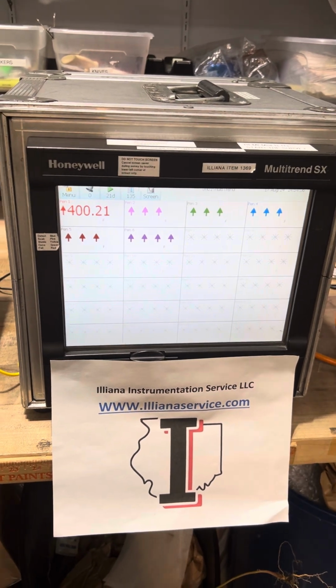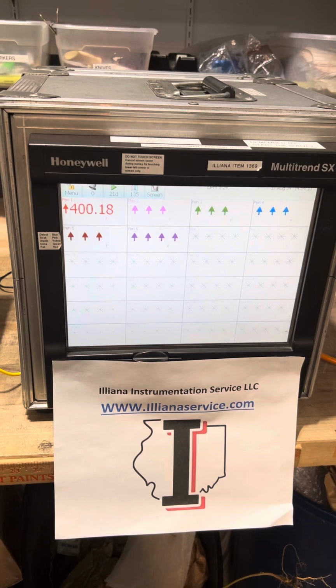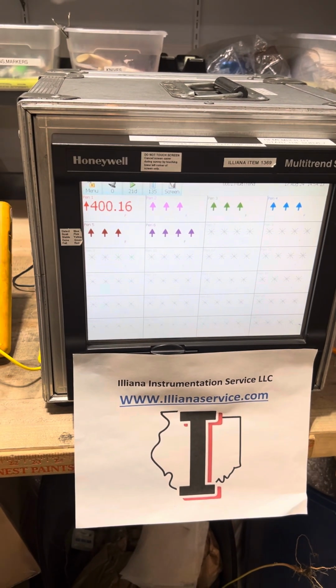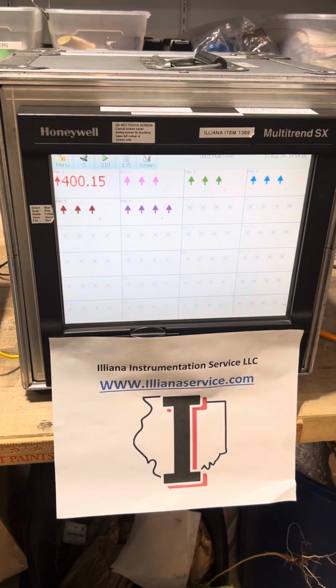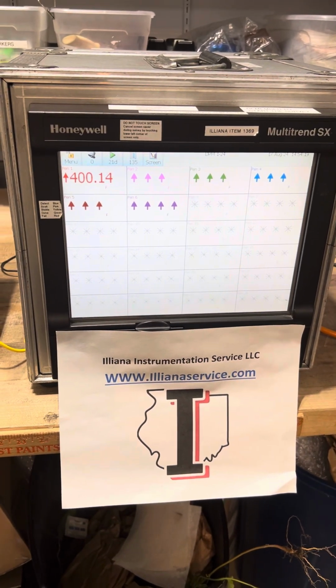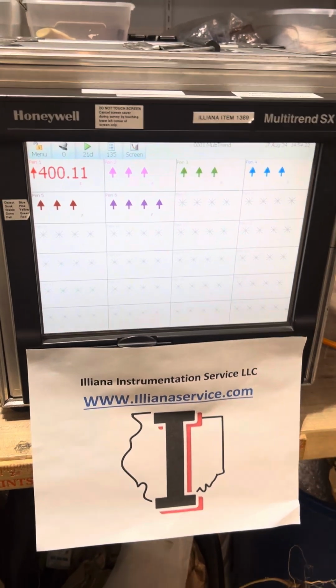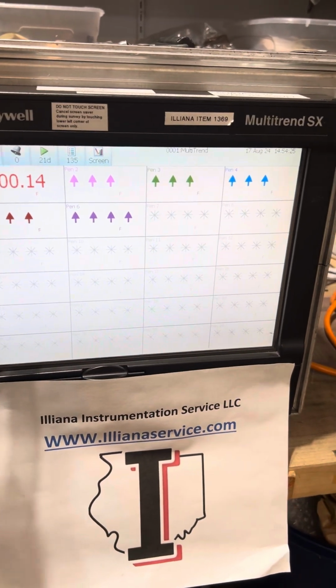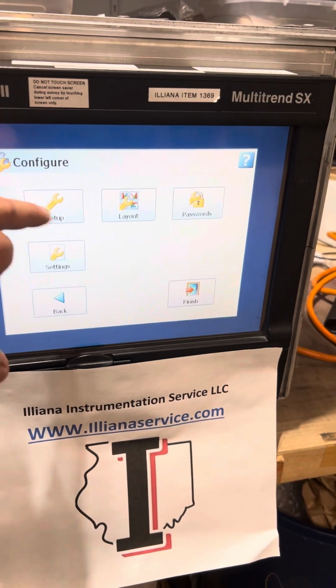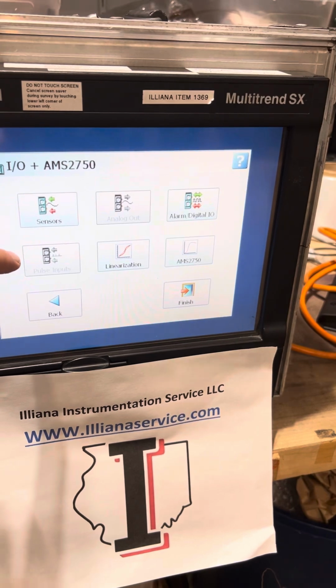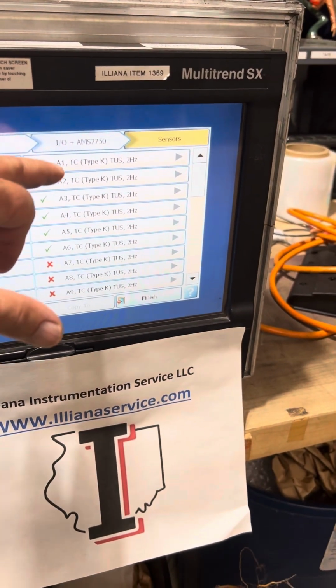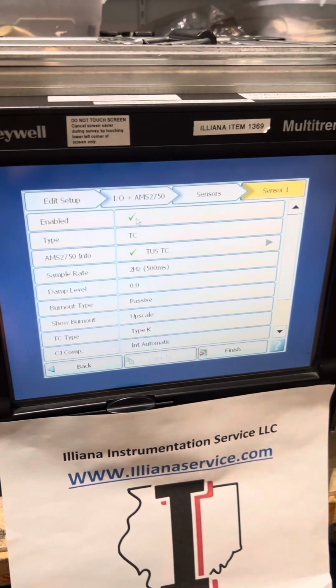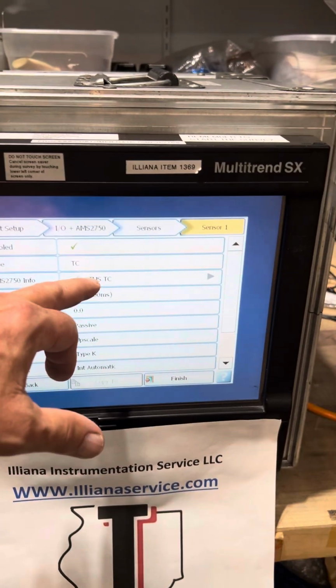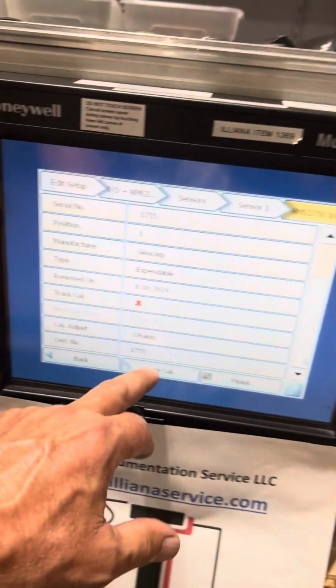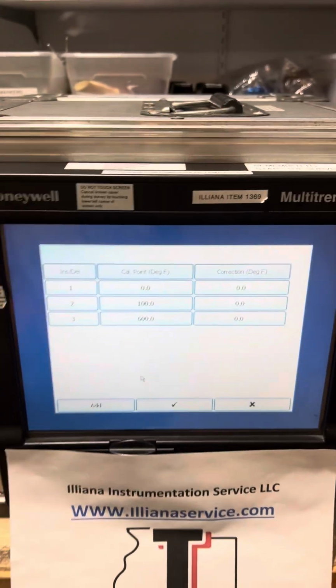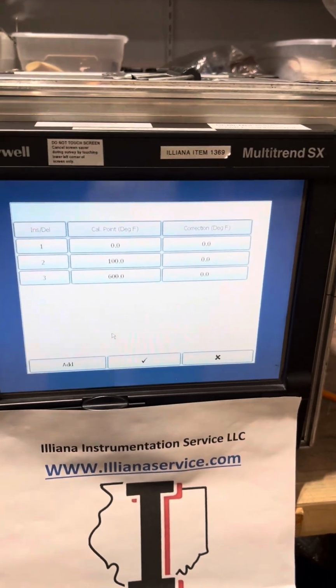The next feature I'm going to show you is how to put in compensation values that are going to correct for the fact that your thermocouple wire that you're using for your temperature uniformity survey is not perfect and in fact has an error, and we have to correct for that error. So we're going to go into here to Configure, Setup, Edit, and I'm going to go to Sensors again, and this time I'm still on Sensor 1, and this time I'm going to hit this AMS 2750 info box, and another option is going to come up here that allows me to do a calibration adjustment, and this calibration adjustment would be for the wire.